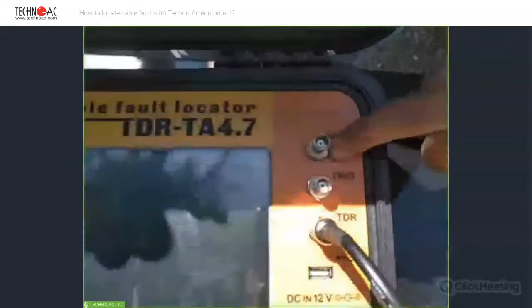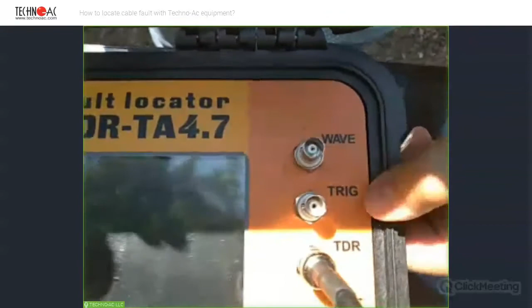As you can see, there are two BNC connectors here. One is called trig and the other one is called wave. The trig is used with high voltage surge wave transmitters. So if you connect this TDR to a high voltage surge transmitter, you can amplify the pulse which is sent to the cable. And if you have a high resistance damage, you will be able to reflect it from the fault and send it back to the device.